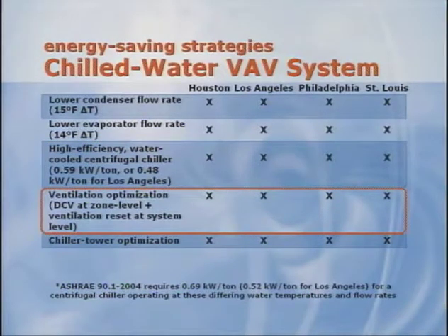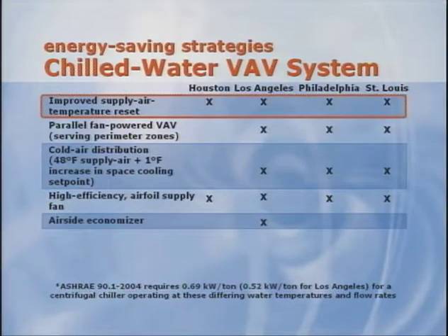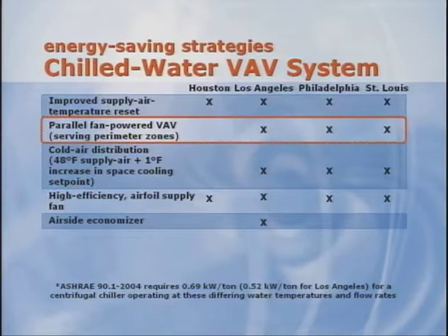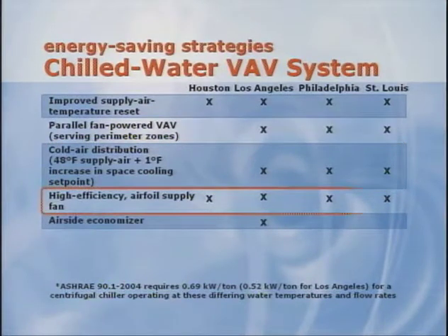The VAV air side strategies are similar to the Rooftop VAV system. The same ventilation optimization and supply air temperature reset sequences were used for all 4 locations. And parallel fan-powered VAV terminals were used in 3 of the locations. For Los Angeles, Philadelphia, and St. Louis, the system was designed for cold air distribution with 48-degree supply air. Since air handlers typically have more fan choices available, a high-efficiency airfoil supply fan was used. Well, we didn't talk much about the chiller plant back in the fan coil system, so let's cover the strategies related to that part of the system now.